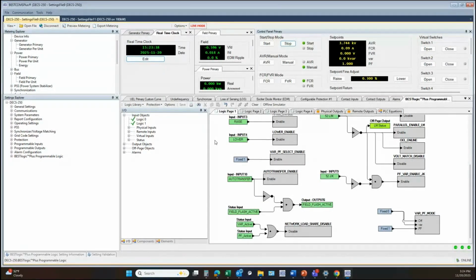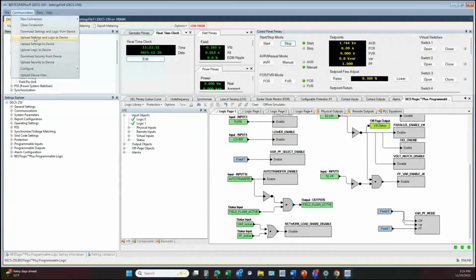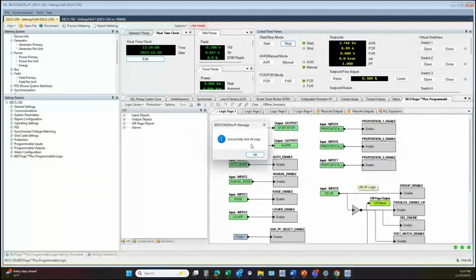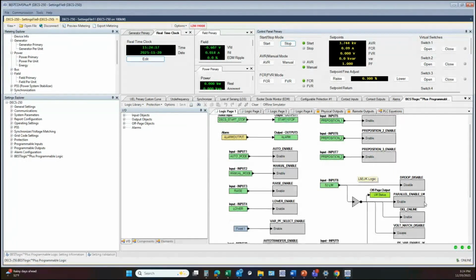It's important to note that the logic is not saved automatically while I'm in live mode, and it's not saved if I'm just sending settings to the unit. I actually have to come up to communication and then upload logic to device, or upload settings and logic to device. So for now, I'm just going to upload logic to device. Again, I'm logging in with capital A for both username and password by default. Then successfully sent all logic. If you don't send the logic, then whatever you create in logic will not be saved in the unit.